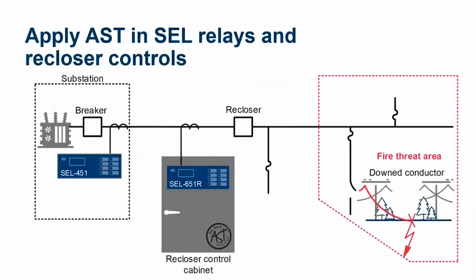Now, this AST is available both in SEL relays, protective relays, and recloser controls. And the nice thing about being able to apply this at multiple locations is that what we see is these high impedance faults, sometimes, remember, we're dealing with currents less than 100 amps. Right? So already we're looking at a small magnitude of fault current, and then we're also picking out the interharmonic energy from that. And some of these higher frequency components are going to be attenuated as they go through the impedance of our power system.